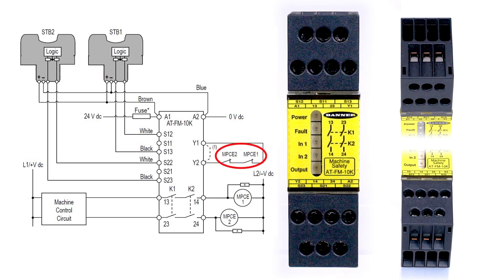If you require contactor monitoring, you will need to wire the appropriate contacts to Terminals Y1 and Y2. If you do not need monitoring, add a jumper wire to these terminals.